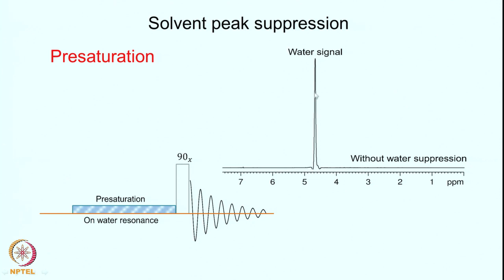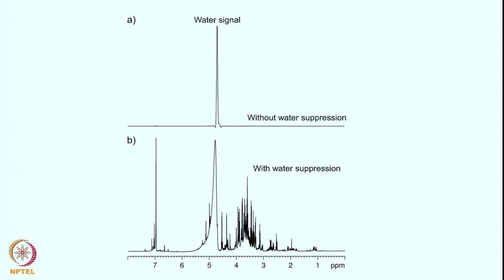The water signal gets saturated while all other signals are not perturbed. This is achieved using a pre-saturation period, where you put a second RF on the water resonance, followed by a 90 degree pulse, and you collect your FID as usual. At this point the water resonance is reduced to a very significant extent, and once you apply the 90 degree pulse along with the other signals, you detect the FID which will not overload the receiver or cause dynamic range problems. The water signal is substantially reduced and you are able to see the other signals of the sample — this is a spectrum of a protein — with good intensities. This is one technique to suppress the water.